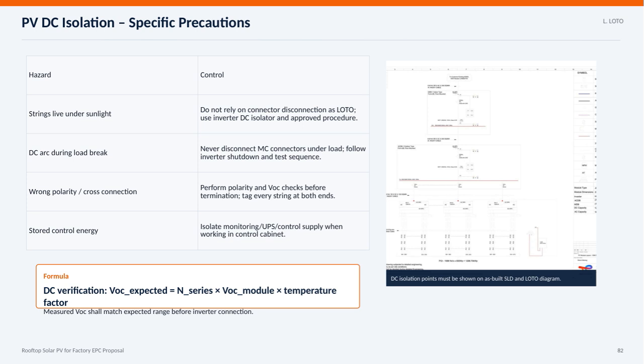To prevent issues like wrong polarity or cross-connection, conduct polarity and open circuit voltage checks before termination, and make sure every string is clearly tagged at both ends. Also, be mindful of stored control energy by isolating monitoring, UPS, and control supplies when working inside control cabinets. The formula here helps verify DC voltage. Multiply the number of modules in series by the module voltage and a temperature factor to get the expected open circuit voltage, or VOC. Your measured VOC should fall within this predicted range before connecting to the inverter. Finally, all DC isolation points must be clearly shown on the as-built single-line diagram and the LOTO diagram to ensure safety and compliance.